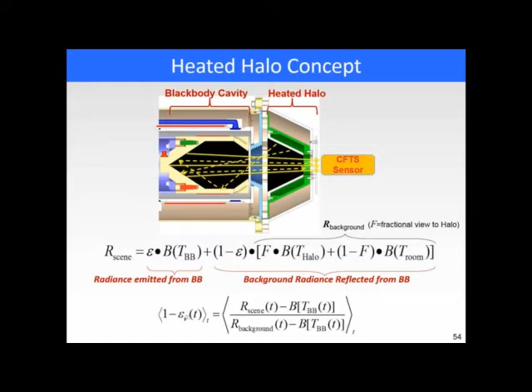So as Bob pointed out yesterday, we have a problem, and then we have a solution, which is to think about this in terms of writing the equation like this. You can solve for this emissivity, but you calculate the emissivity once every time you calibrate the instrument. And so then you're averaging calibrated measurements over time. You do not require this instrument to have stability over the multiple hours it takes to get this within the uncertainty you need. So that was a key to making this work.